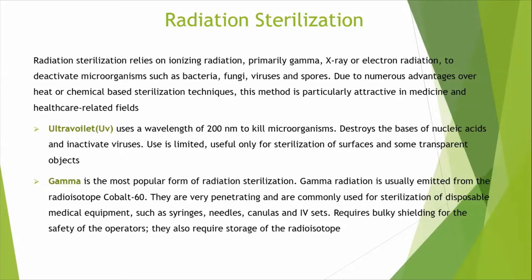Gamma radiation is the most popular form of radiation sterilization. It is usually emitted from the radioisotope cobalt-60. Gamma rays are very penetrating and are commonly used for sterilization of disposable medical equipment such as syringes, needles, cannulas, and IV sets. This method requires protective shielding for the safety of operators and storage of the radioisotope.